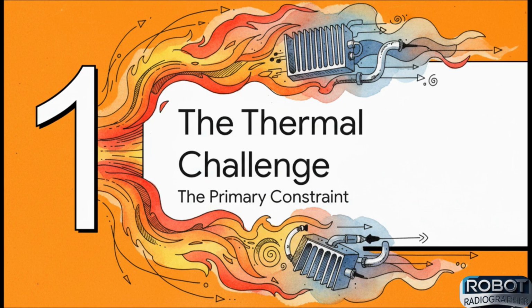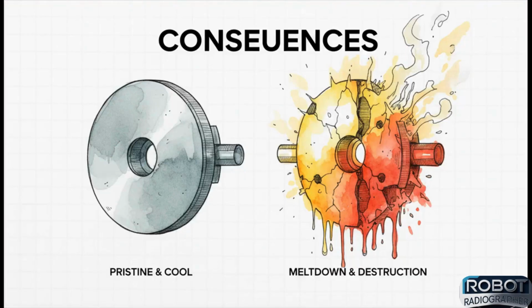Seriously, managing this colossal amount of heat isn't just some side project in X-ray design. It is the single biggest challenge. It dictates pretty much everything: the power, the size, and the lifespan of every single machine out there. So what happens if you don't manage that heat? The consequences are, well, they're extreme. The little part inside where the X-rays are actually created, it's called the tungsten target, would be vaporized in a single use. The machine would literally destroy itself from the inside out.